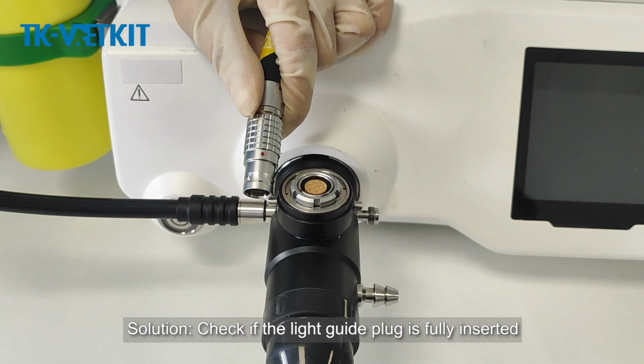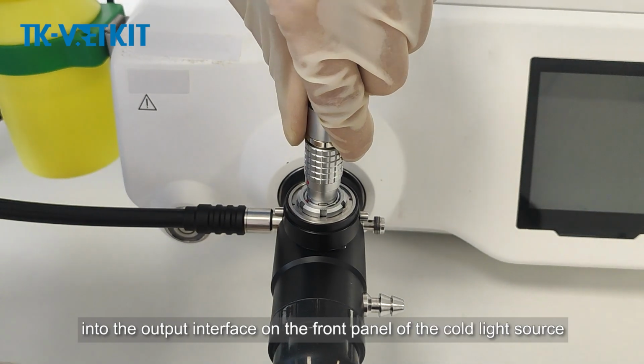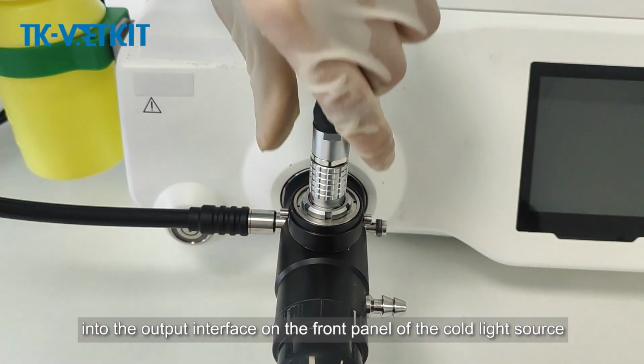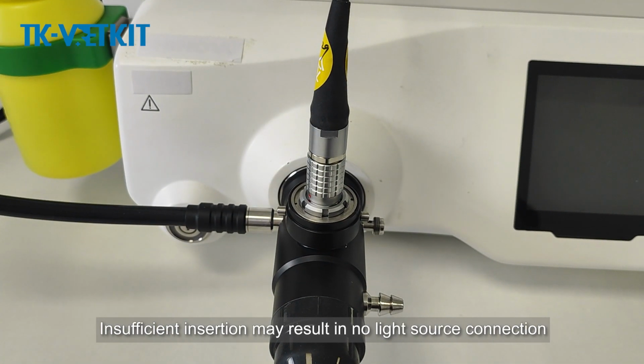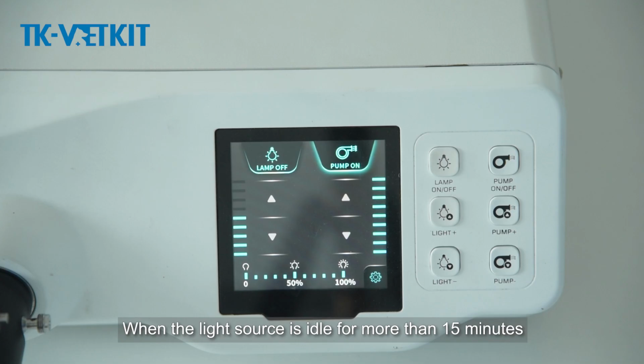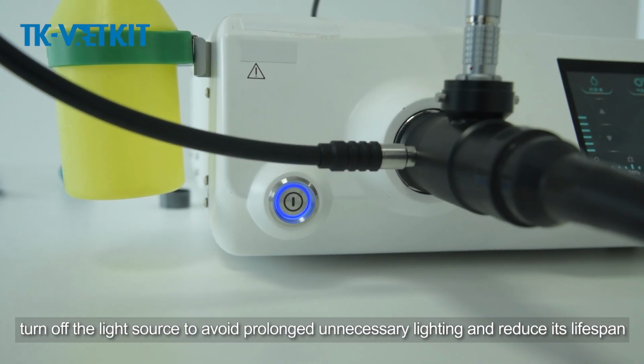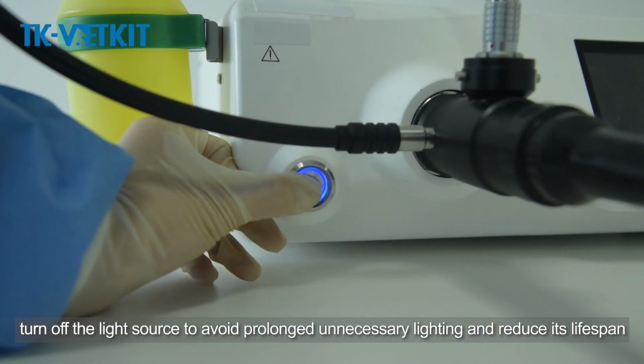Solution: check if the light guide plug is fully inserted into the output interface on the front panel of the cold light source. Insufficient insertion may result in no light source connection. When the light source is idle for more than 15 minutes, turn off the light source to avoid prolonged unnecessary lighting and reduce its lifespan.